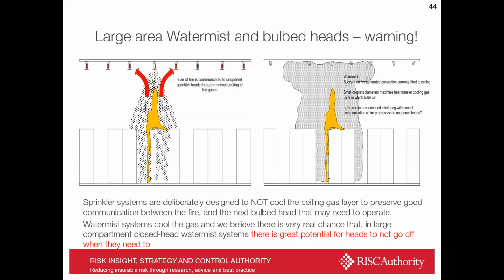Now, it may not be known to many people, but sprinkler systems are deliberately designed not to cool the ceiling gas layer, because the temperature at the ceiling is the only means with which the sprinkler head can communicate with the size of the fire below. So the next sprinkler head in an array to go off needs to understand what temperature the fire is and whether that bulb is needed. So the droplets are very large, so they don't cool the gas layer, and a great deal of effort goes into sprinkler design to ensure that is always the case.